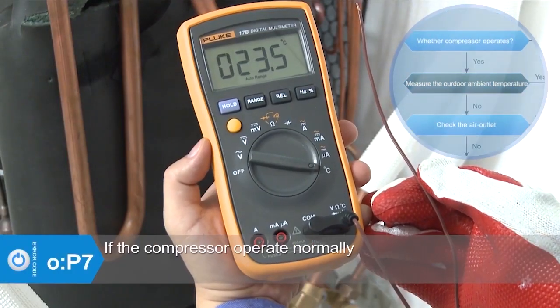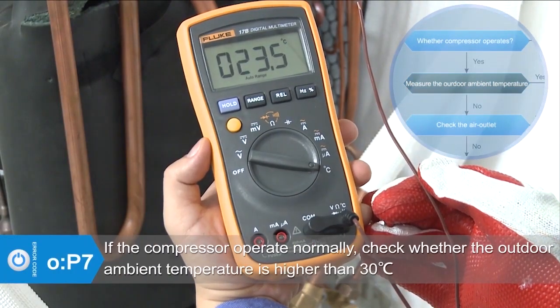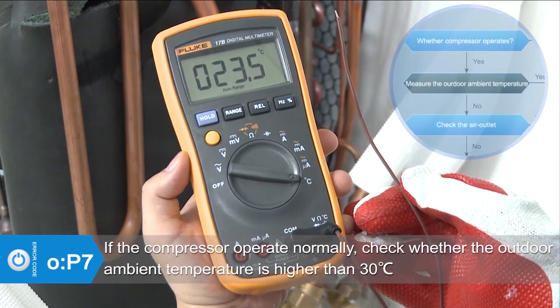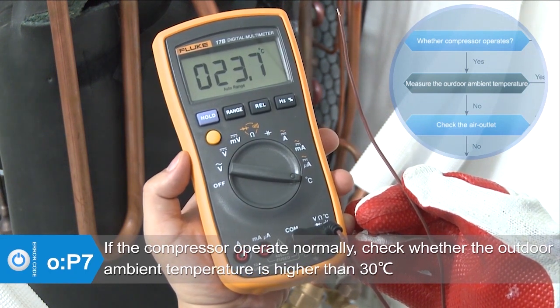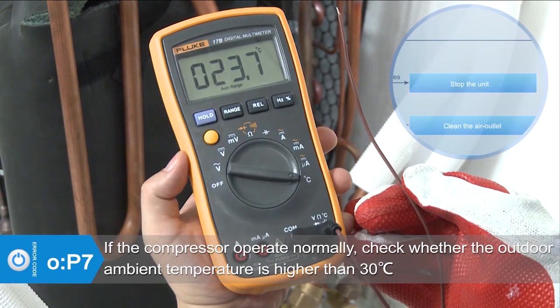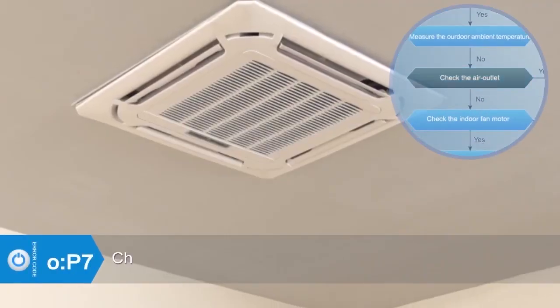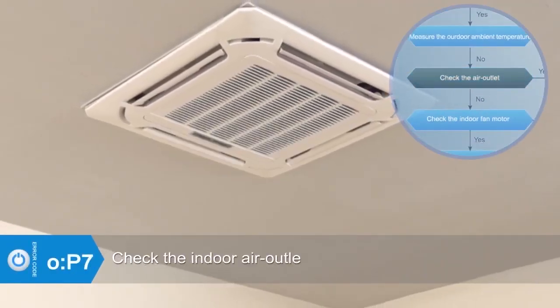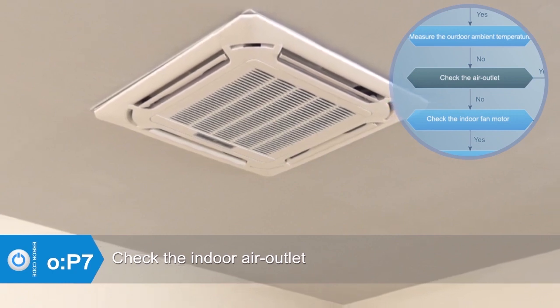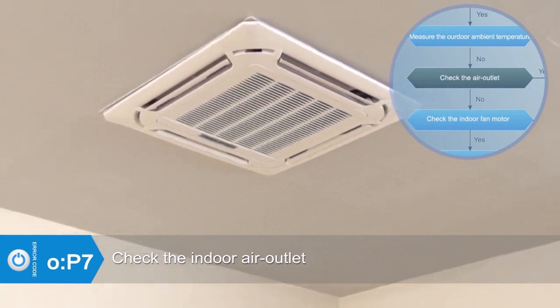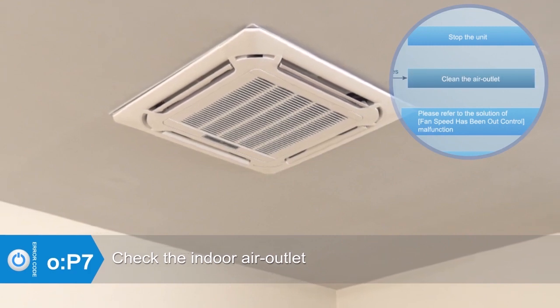If the compressor operates normally, check whether the outdoor ambient temperature is higher than 30 degrees Celsius. If the temperature is higher than 30 degrees Celsius, stop the unit. If the temperature is lower than 30 degrees Celsius, check whether the indoor air outlet is blocked. If the air outlet is blocked, clean the air outlet.